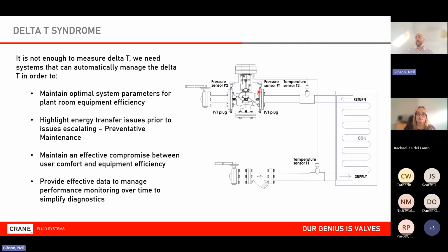So you can see an example here. This is just a larger setup. This is an electronic PICV driven by pressure sensors, pressure transducers, you can see there, P1, P2, and by temperature sensors as well, T1, T2, installed on the pipework. T1 is flow, T2 is return. And what I can now do is monitor and control based on these. These are separate Modbus registers, both T1, T2, and the resultant DT. We can then generate power based on positional feedback. That's a separate register as well. So we can use this as a form of heat meter, albeit not a billable one in the sense that it's not MID approved, but then the applications we're talking about, we've seen examples on heat pumps, on AHUs, even on individual terminal coils, where we wouldn't necessarily bill, but we do want to get that energy information out of the system.